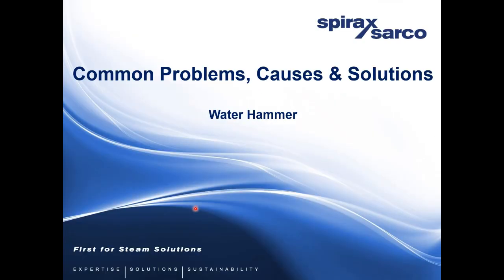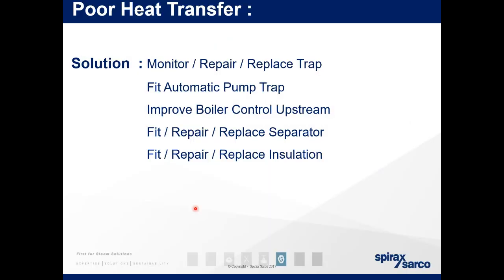So anybody have any questions at that point before I hit water hammer? Yes, there's one new question. So looking at the composition of condensate, that is 99.6% flash steam and 0.4% condensate, does that imply that it is not cost effective to invest in condensate recovery?